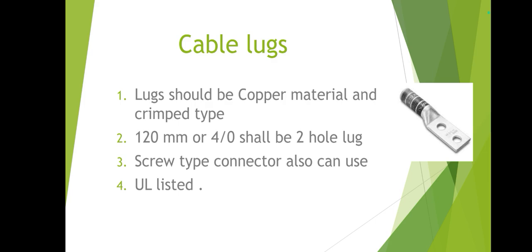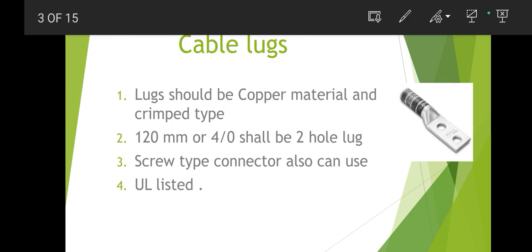For 120 mm² cable, two-hole lugs should be used as shown in the pictures. We can also use screw type connectors. These items should be UL listed, the manufacturer should be approved, and during material receiving we must verify that the manufacturer is on the approved list.